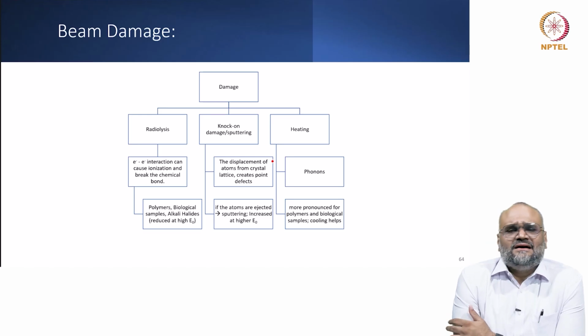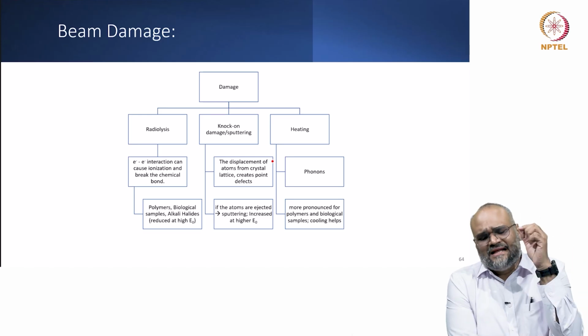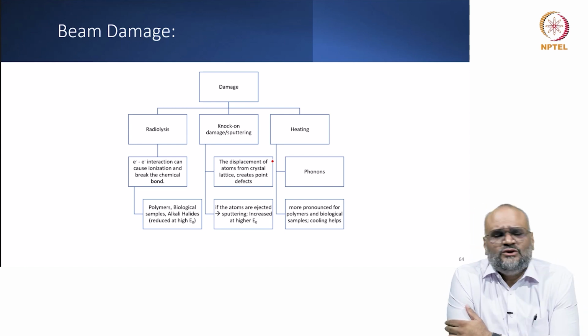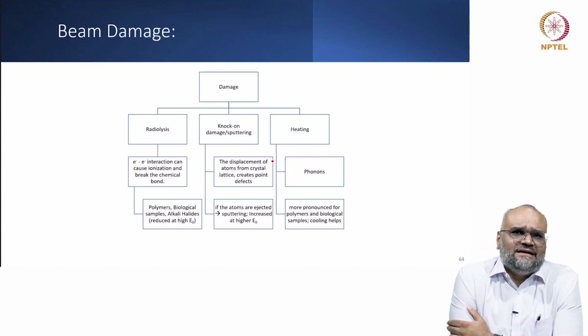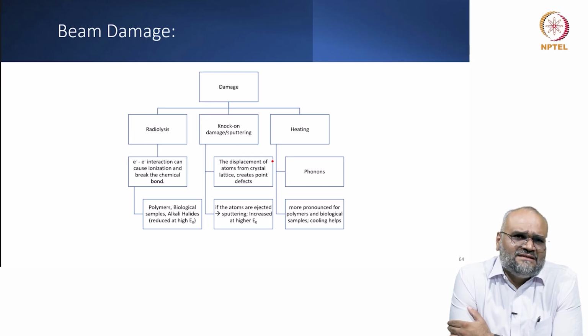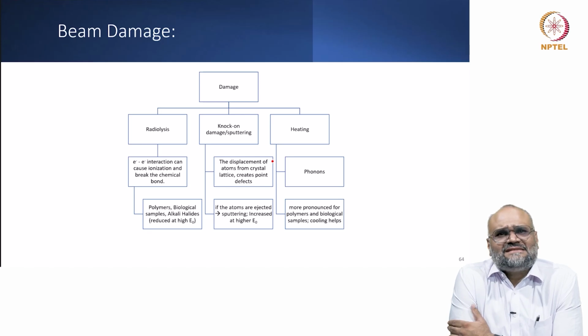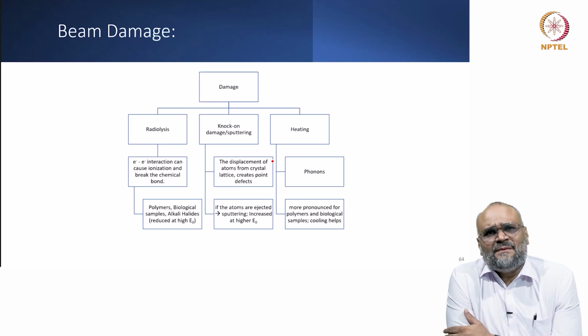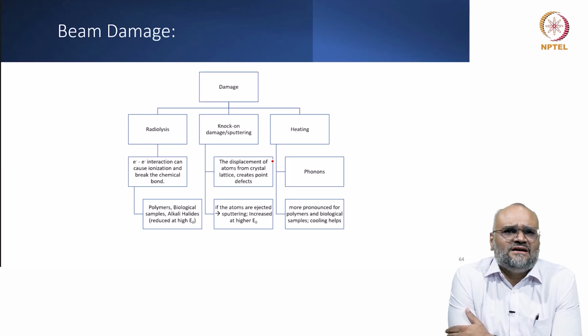This is when the complete momentum transfer from the electron beam happens to kick out a nucleus from the crystalline lattice. This is where you have to overcome the threshold of the binding energy, and this is typically a 1 in a million probability, but it still happens more often over repetitive events. Such damage is called knock-on damage or sputtering.